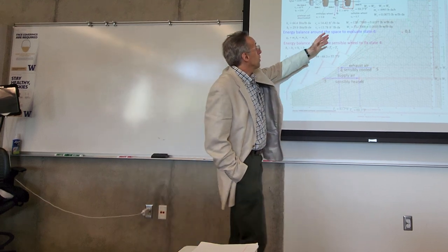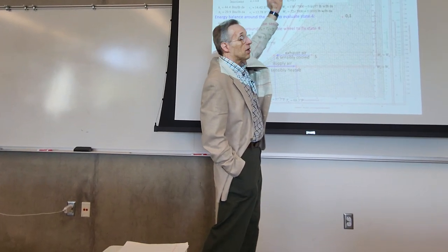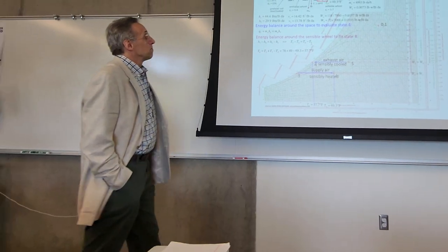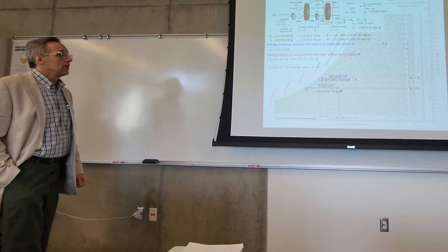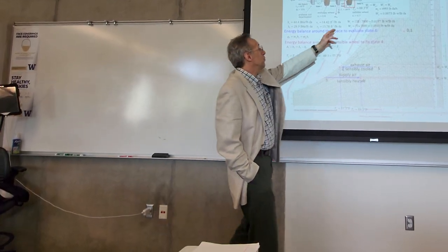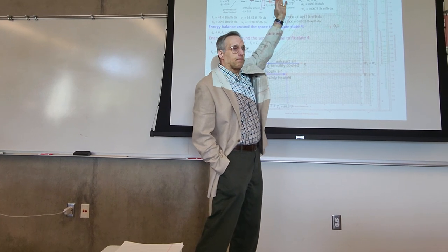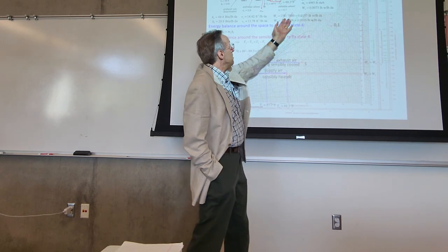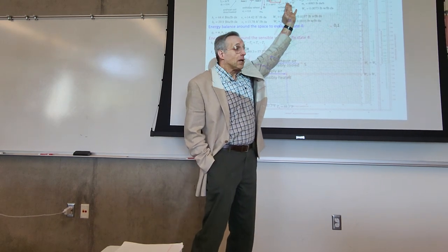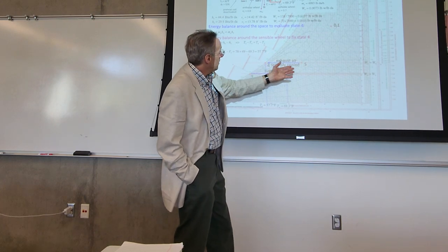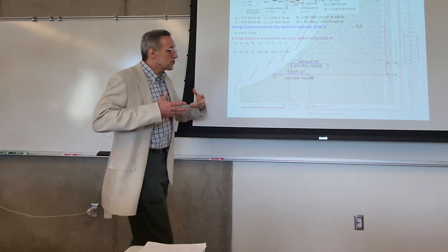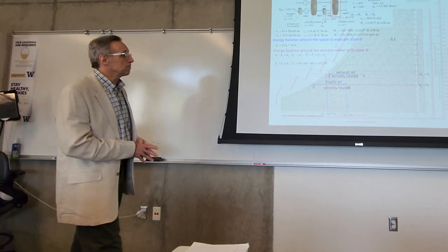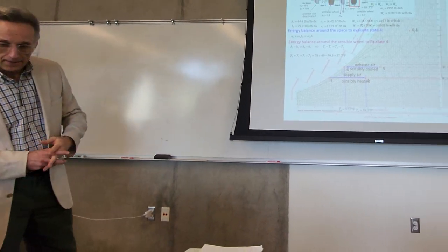And at this point, we've already got the moisture to where we need it coming off the cooling coil, so there's not really any need to further adjust the moisture. And in most applications, we don't even need this. The temperature is satisfactory, maybe a little cool, but it will adjust when it gets entrained in the air in the space, plus it mixes with the air that's coming off the other conditioning system that complements the DOAS system.